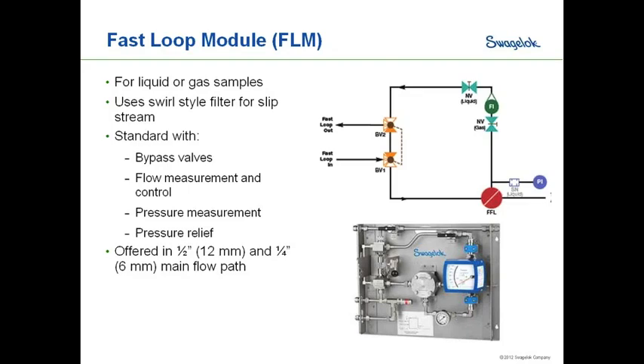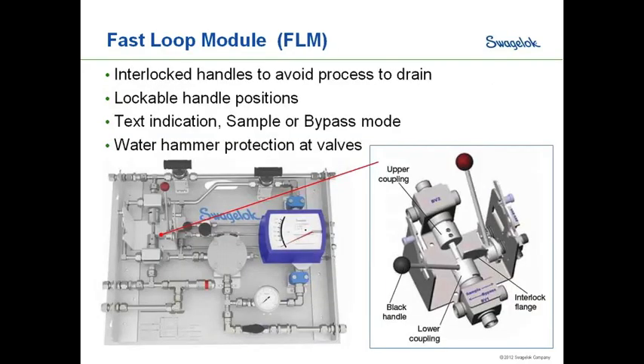Both versions are built similarly and look very similar to each other. One notable feature is that by standardizing the design, we've been able to eliminate quite a number of fittings — there are some welded joints, and we've constructed connectors to do the job. We've also used VCR fittings, which enable you to remove components such as a filter or valve without disconnecting everything — just undo the nuts and it pulls straight out with essentially zero clearance.